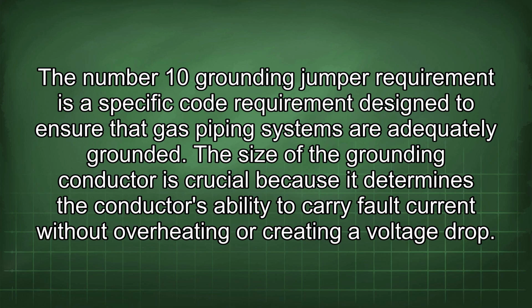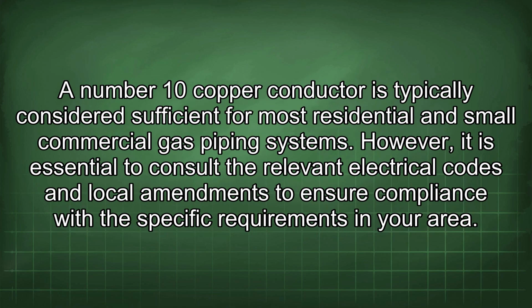The number 10 grounding jumper requirement is a specific code requirement designed to ensure that gas piping systems are adequately grounded. The size of the grounding conductor is crucial because it determines the conductor's ability to carry fault current without overheating or creating a voltage drop. A number 10 copper conductor is typically considered sufficient for most residential and small commercial gas piping systems. However, it is essential to consult the relevant electrical codes and local amendments to ensure compliance with the specific requirements in your area.